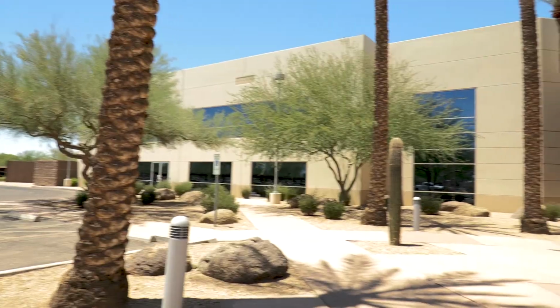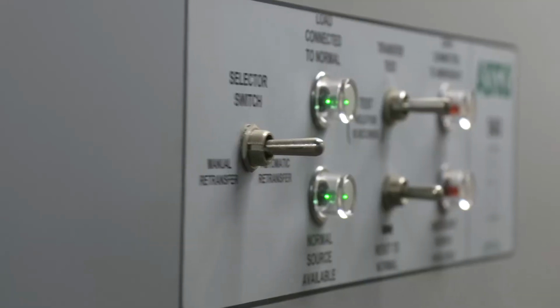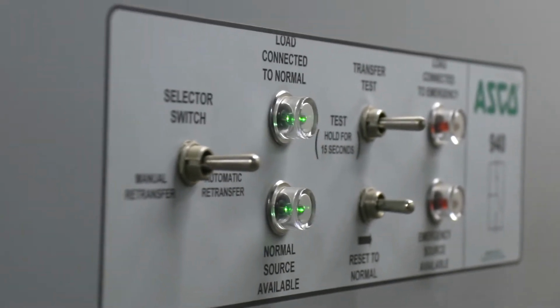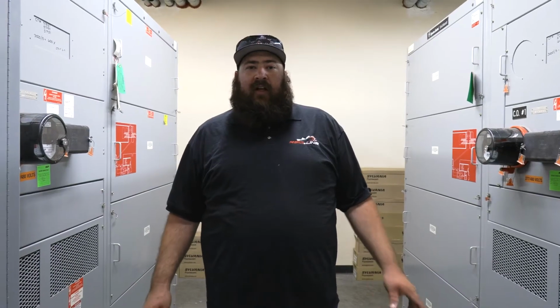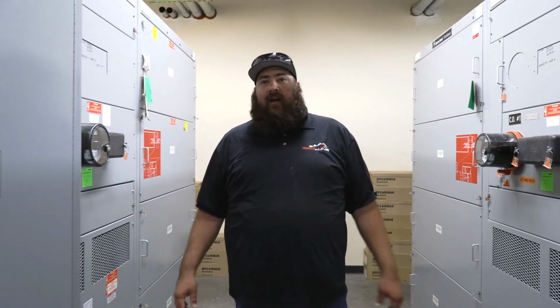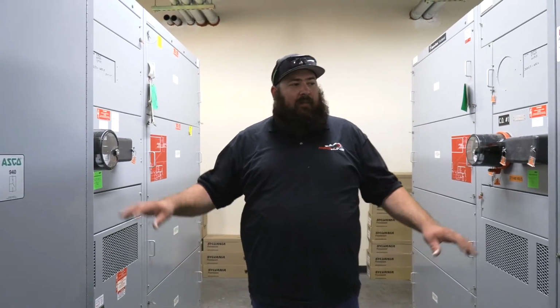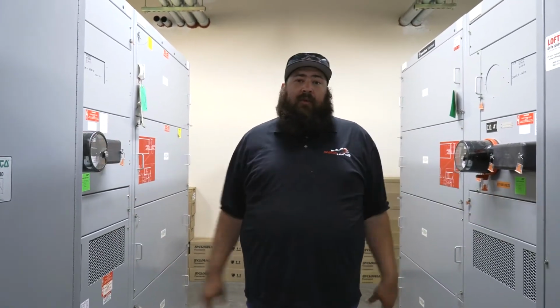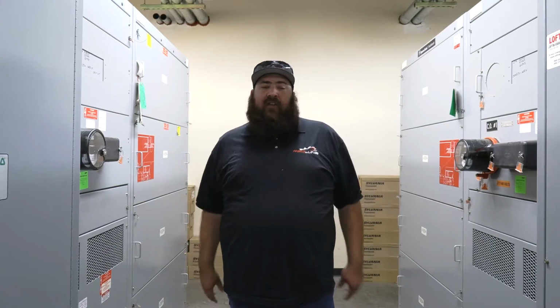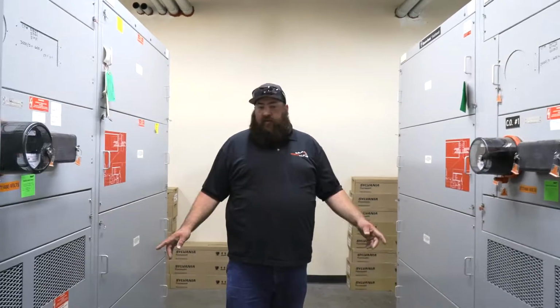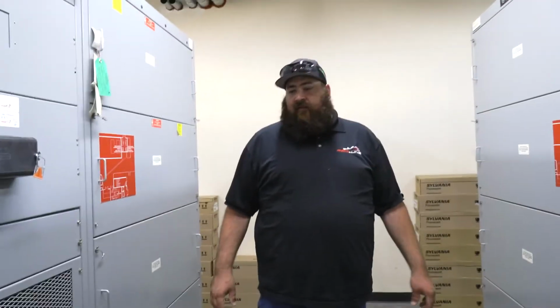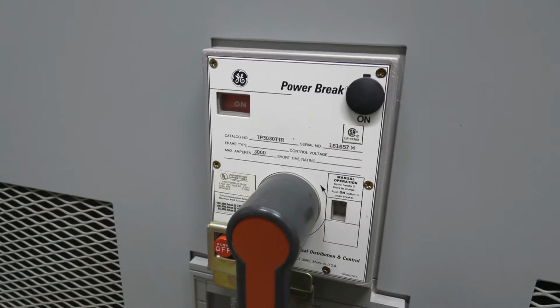What was nice with this shutdown, if we come back here, both of these systems, these are transfer switches. We're able to keep the whole building running on their two generators that they have outside while we had this shutdown. So they went down for a few minutes when we shut it off, and then a few minutes when we turned it back on. But it's a really nice setup that they are able to back up the entire building, both sections, with two generators, so they can keep this whole thing going. 3,000 amp switches, main switches, which are these guys down here.